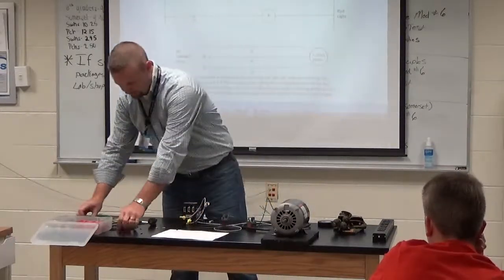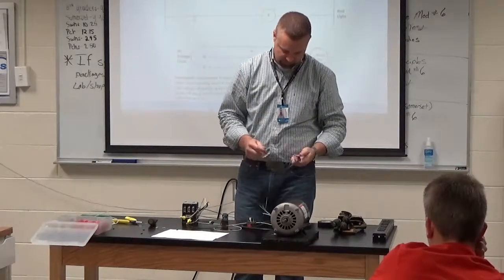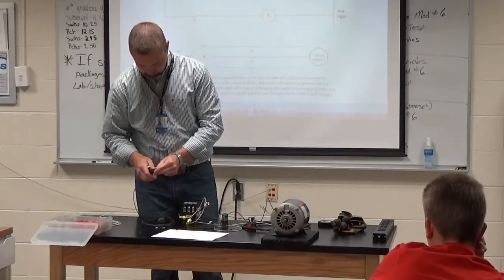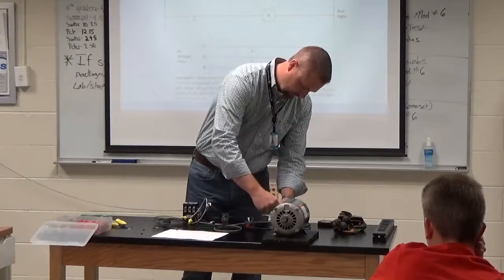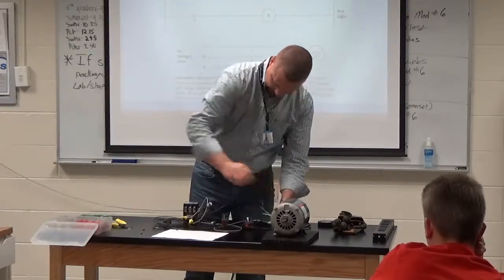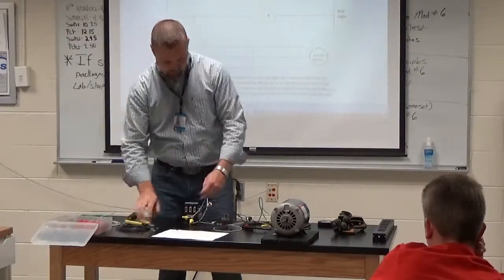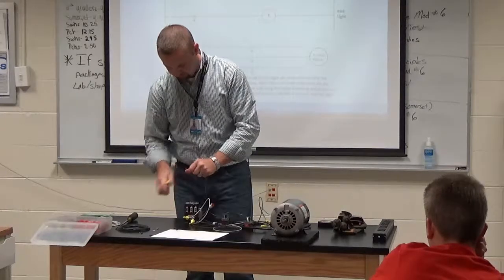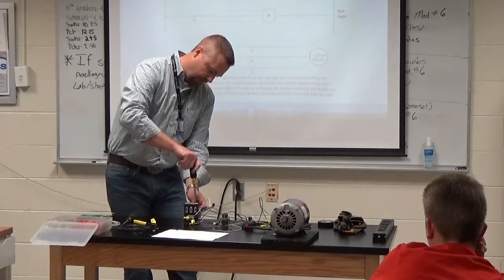Now our last step is running direct power to my starter for my motor, because we're going to be operating a simple 120 volt electric motor in this circuit. Now I must tie back into my direct power to do this. I run a direct power wire over to the top or bottom side of our starter, guys. Top. Yes, I always go in with power on the top side, and I come out the bottom and then go to the motor, correct? On a three-phase system, we would have line 1, line 2, and line 3. But in this case, with 120 volt, we've got a hot wire, a neutral, and a ground.